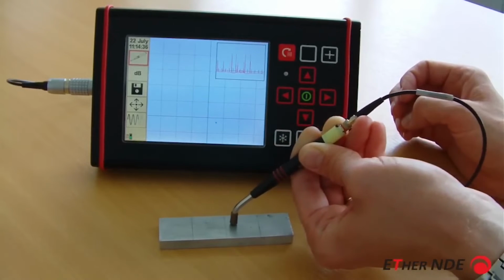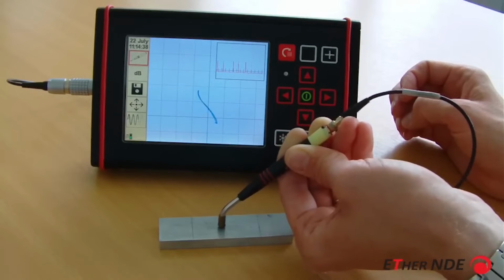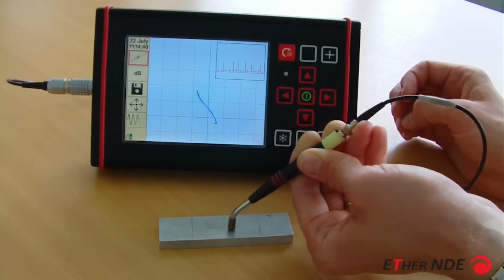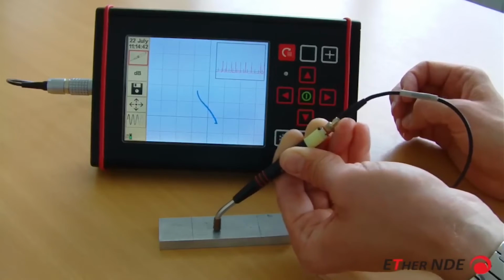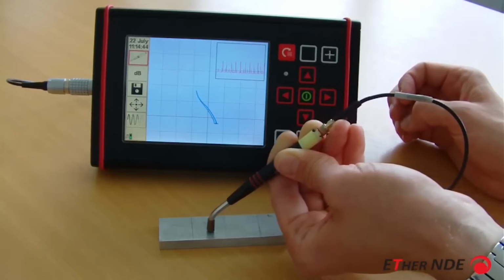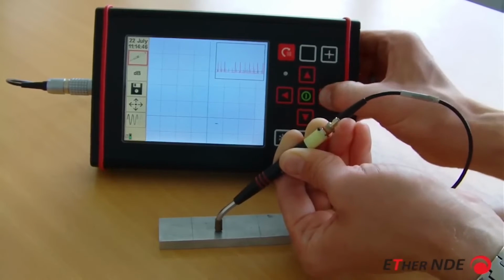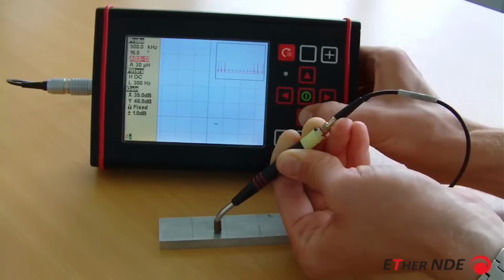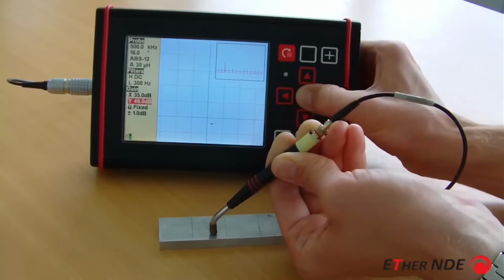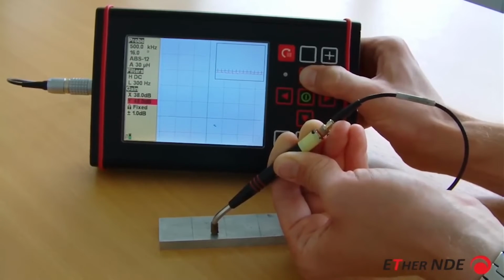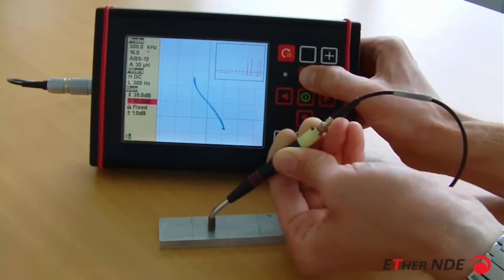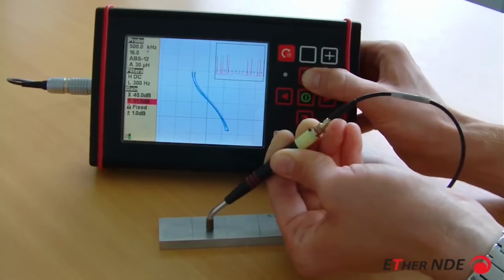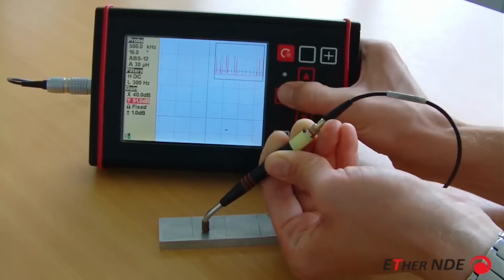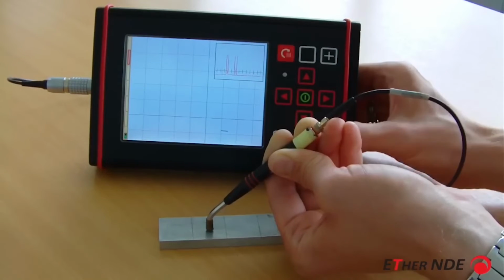Now obviously the sensitivity can be changed by simply varying the gain. So this is the half a millimeter slot. Again, if that needs to be bigger, it's very simple to go to gain, and I can just change the gain to make the signal larger. Here we go, I can do another balance.